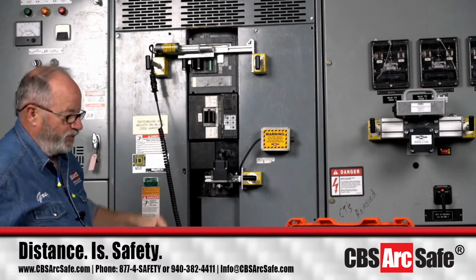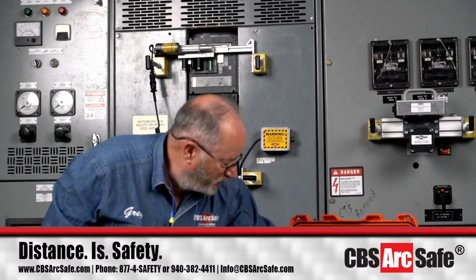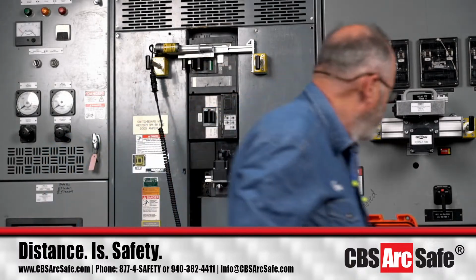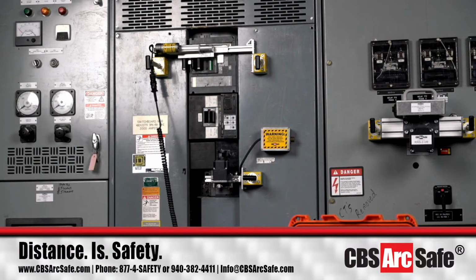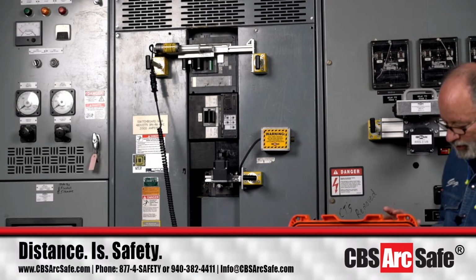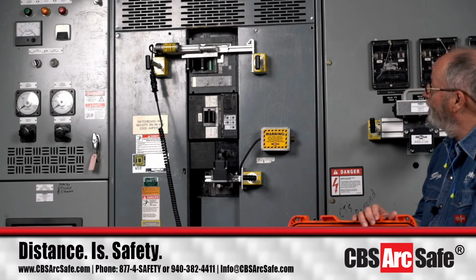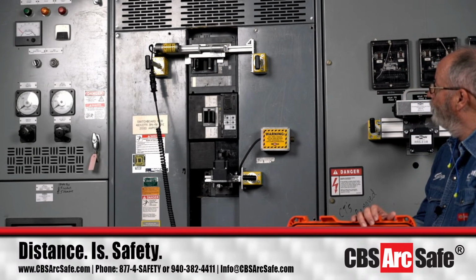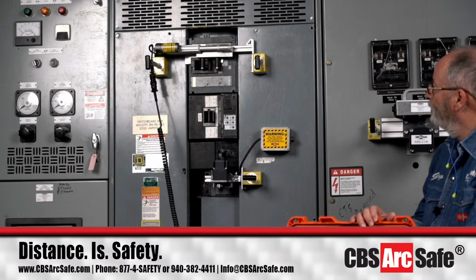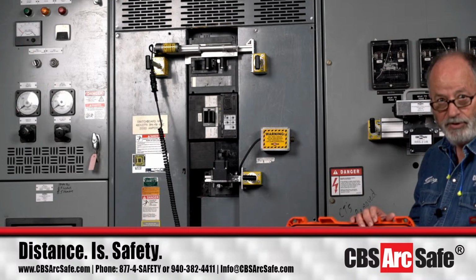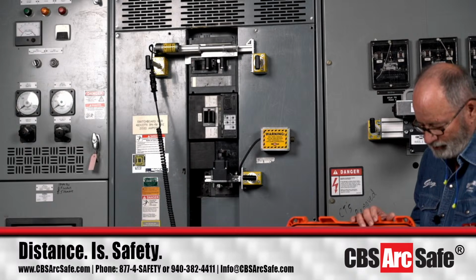The breaker's in the open position. We'll turn our RSO1 on. Let me step over to this side so I'm out of the way and you can see this. So now we're going to hit the close button, hold it down for the entire duration of the operation, then for a trip...